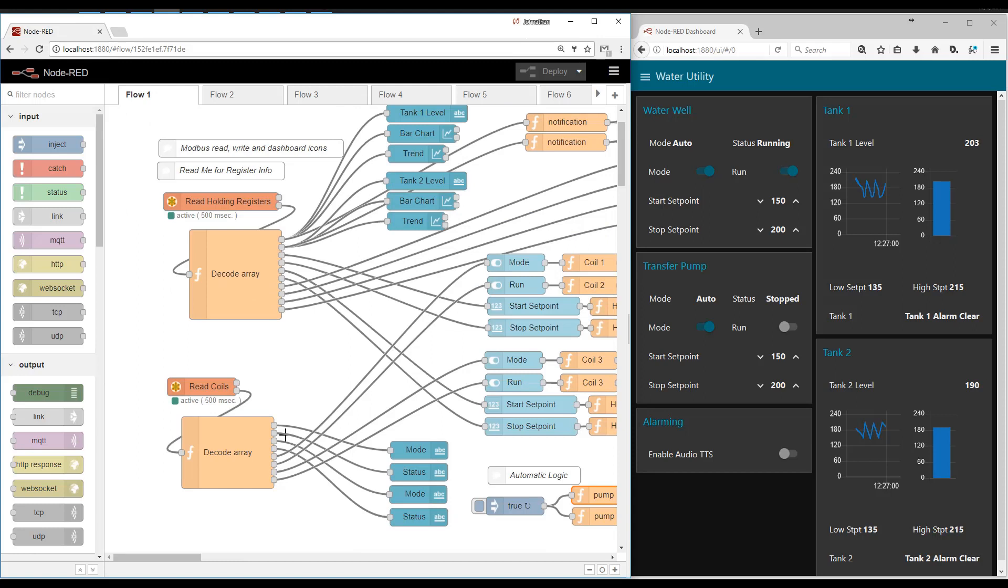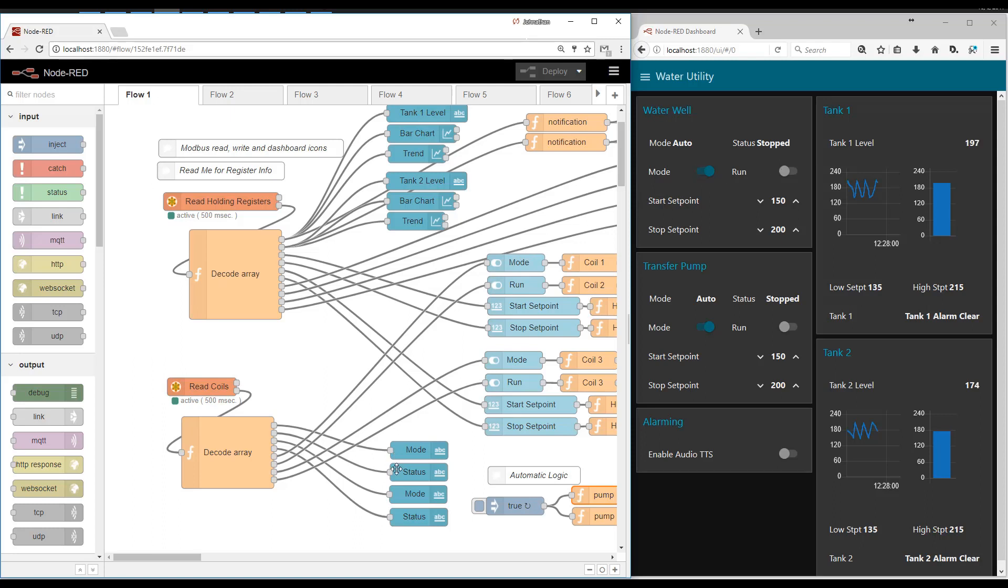The core of the flow here is where we read holding registers and we read coils. So coils are the discretes. So those are the toggle switches seen here. The modes and the statuses. And then this one up here reads the holding registers, which are all of the analog values.